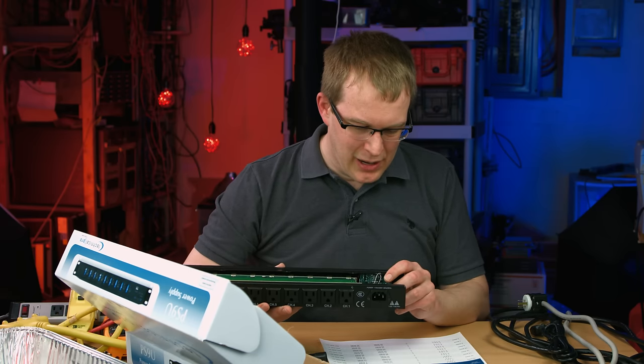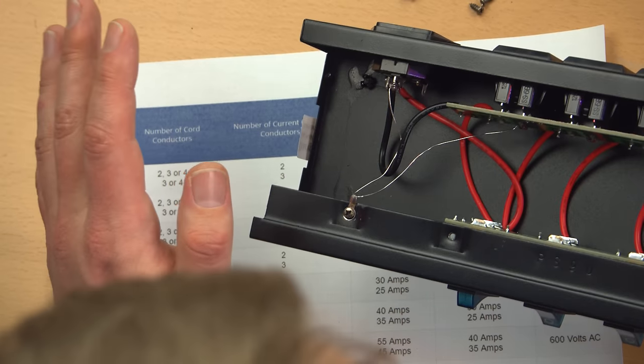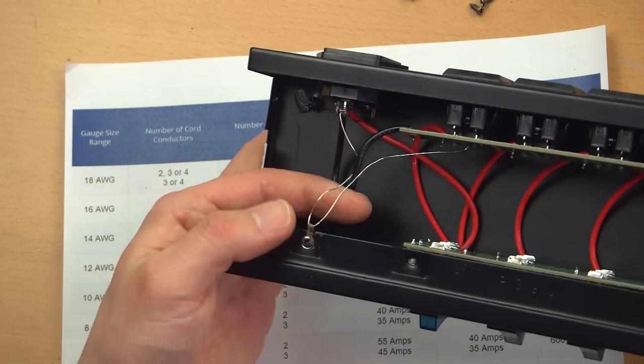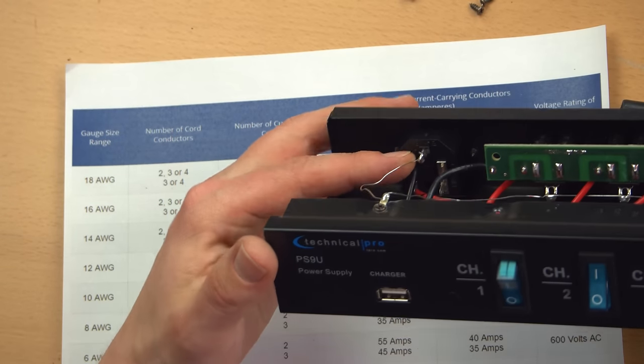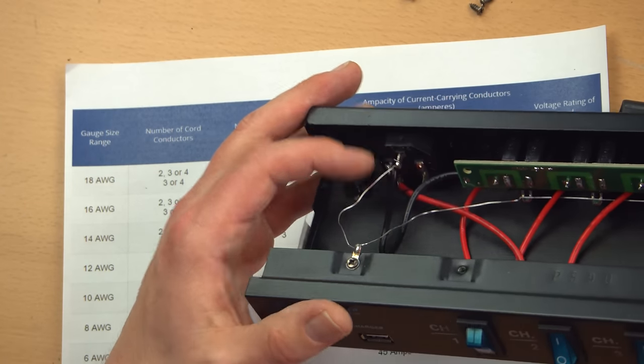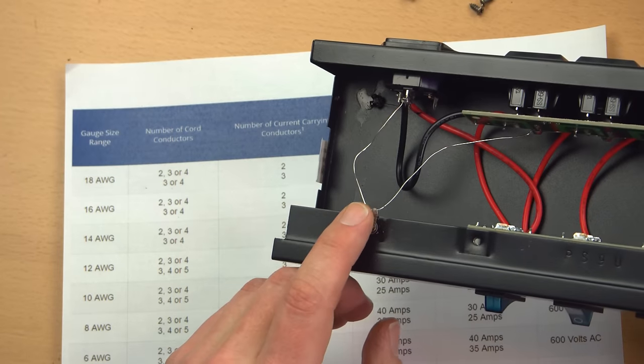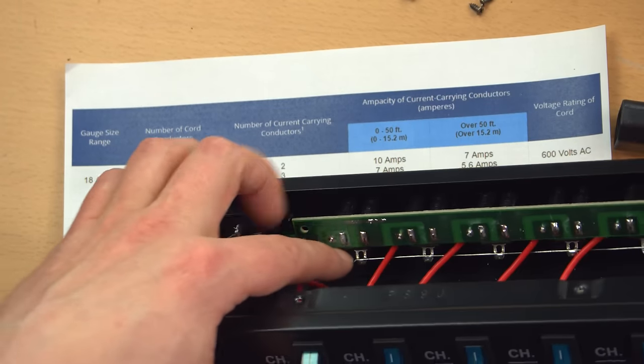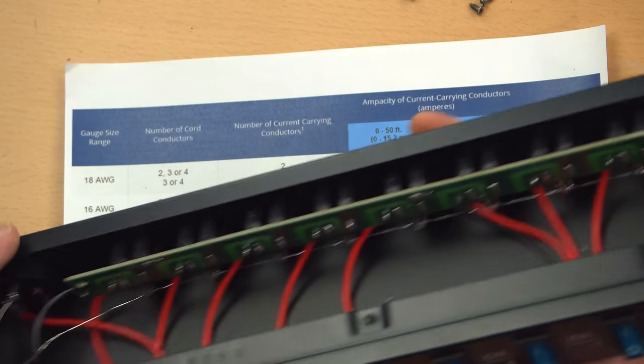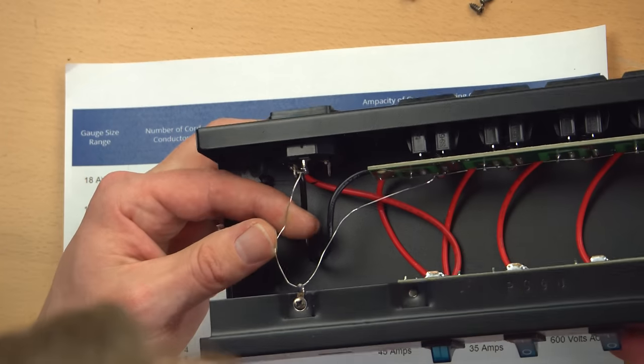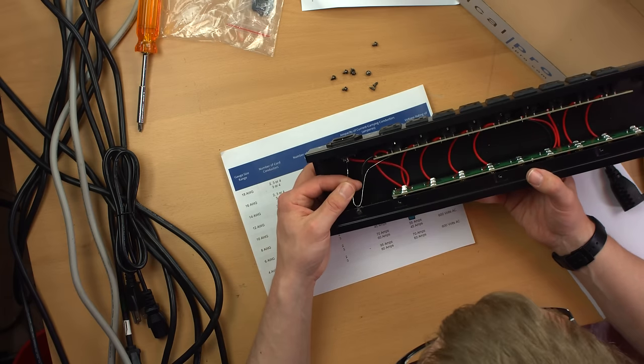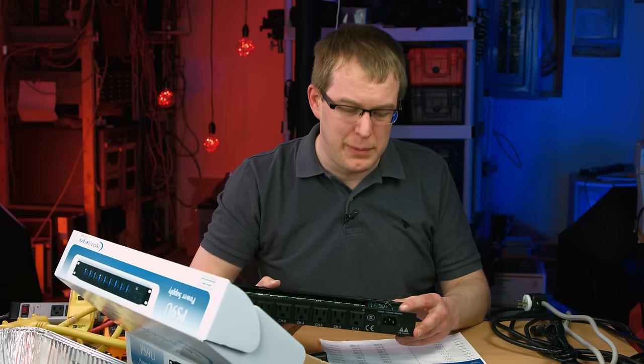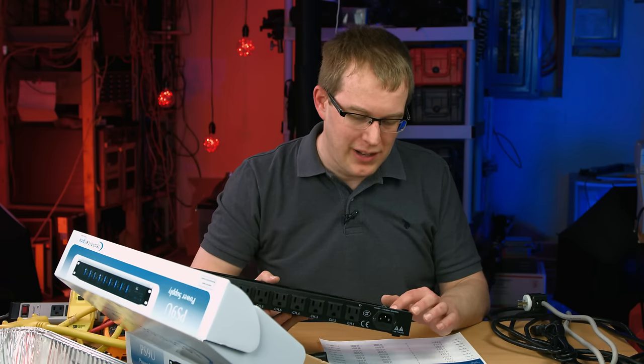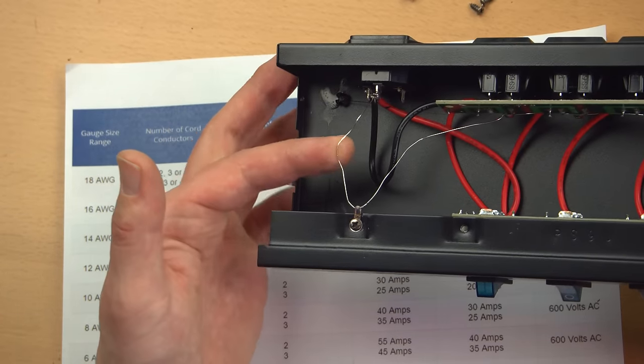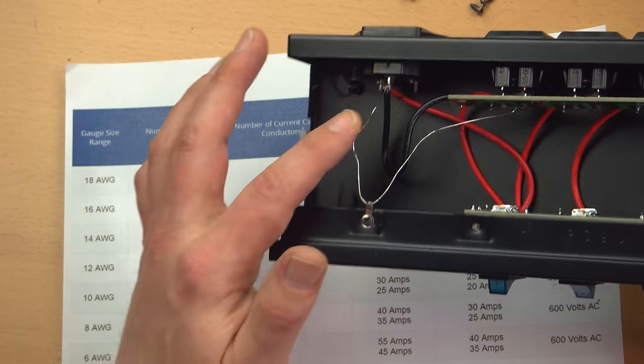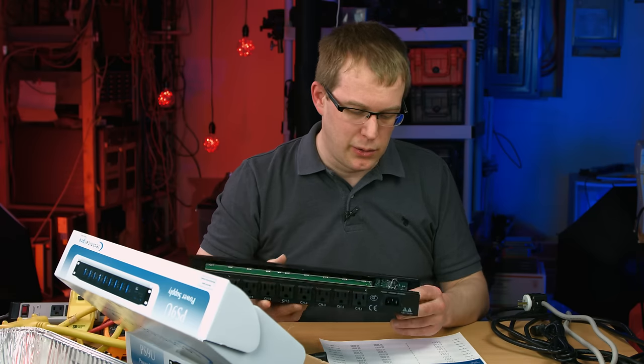Now, one thing which right away I can just tell off the bat is terrible about this. This is the grounding conductor. It comes from the grounding pin on this plug receptacle thing, goes up to the chassis. At least the chassis is grounded, that's nice, and then goes across to each of the receptacles in turn. It's very thin, and it's clearly aluminum or some alloy similar to aluminum. That's way undersized, because if you have a dead short from live to ground, this is just going to disappear. I mean, it's basically fuse wire. And then you no longer have a ground on any of your equipment or on the chassis.